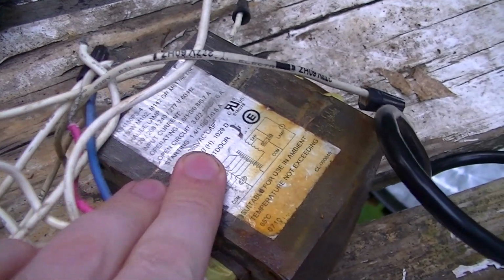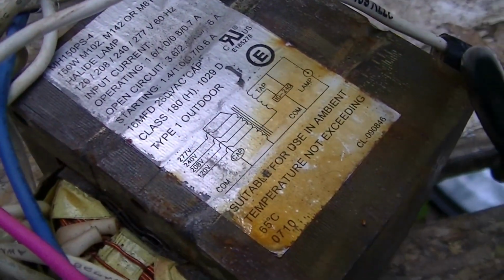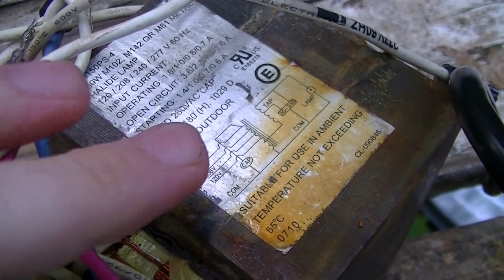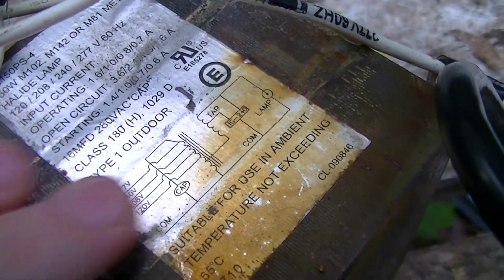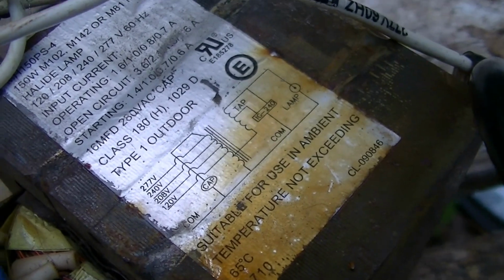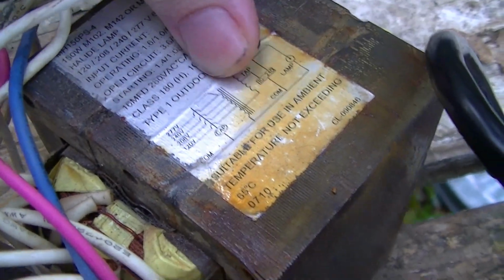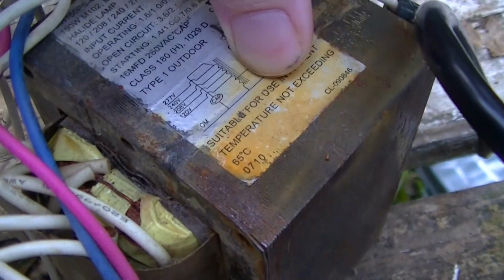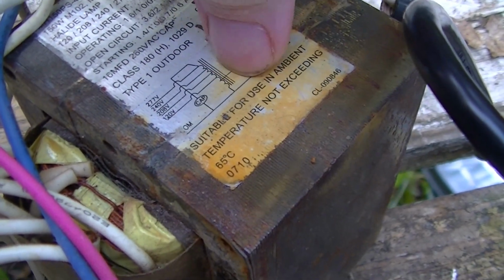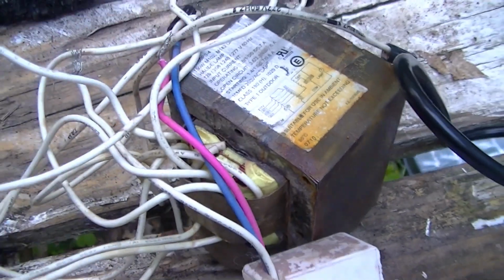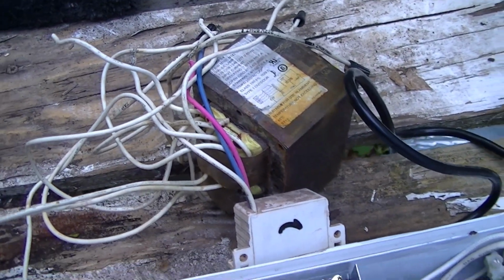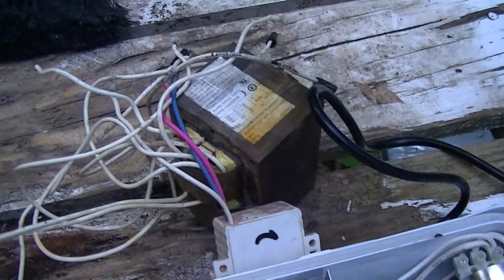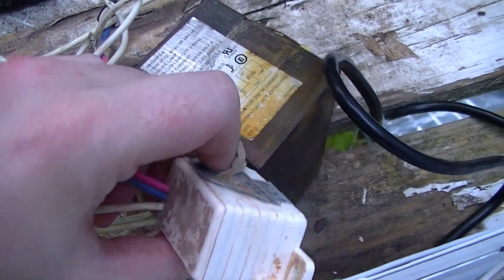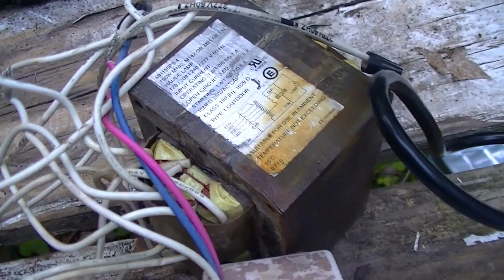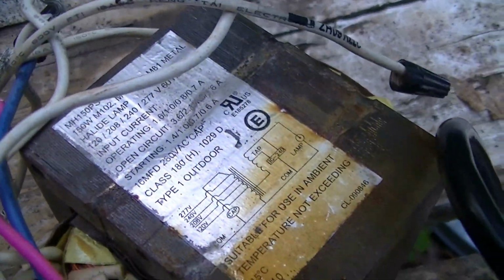This being what's known as an HX, or high leakage reactance, auto transformer ballast. Because you can see that the potential supply auto transformer is directly connected to the choke. With a peak lead or constant power auto transformer ballast, the capacitor would be wired in series with that connection there, and there'd be 2 extra wires coming out of the ballast to connect to the capacitor. Or for lamps which didn't require igniters, so high pressure mercury and probe start metal halide, the capacitor would be connected in series with the lamp there because there wouldn't be an igniter.